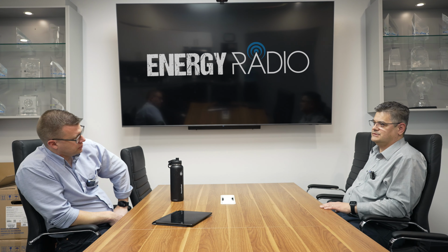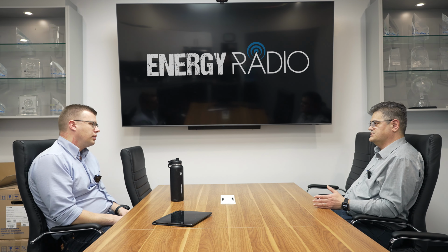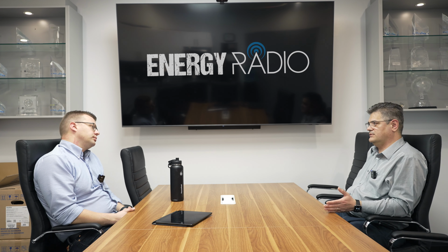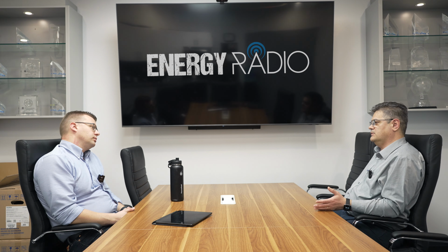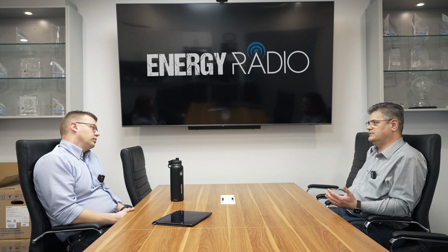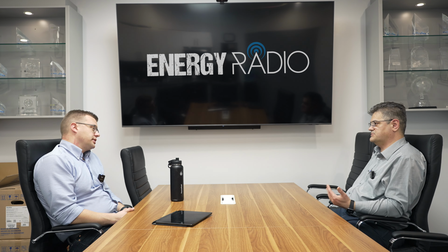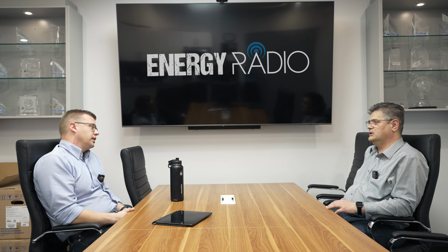Is that because you're predominantly islanded from the grid? One, because of that—but if anything happens on the grid, the breaker will open and we stay on island mode, and our plant is protected. We had one incident, a really bad storm where the overvoltage traveled so fast through the breaker that it tripped the gas compressor, and then everything shut down from there.